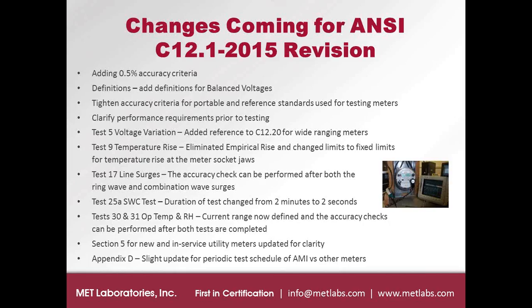There's going to be a 0.5 accuracy class in there now, whereas traditionally in the past, the C12.1 standard was really considered a 1% accuracy standard, a 1 accuracy class. There's some expanded definitions, particularly on balanced voltages, and tightened accuracy criteria for both portable and reference standards used for testing meters in the field or in the lab. A bit of clarification on the performance requirements prior to getting into a test program.